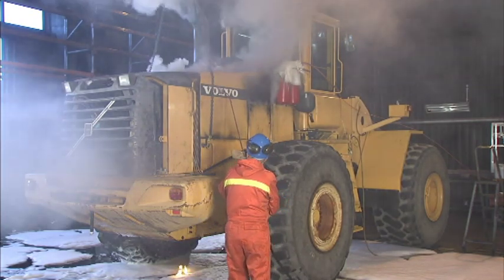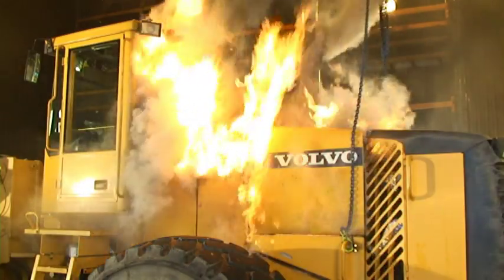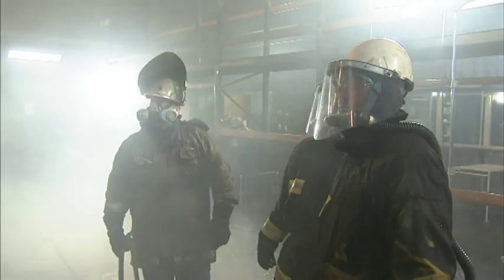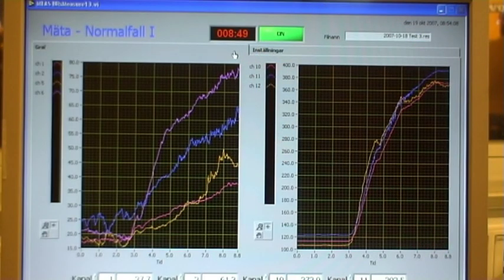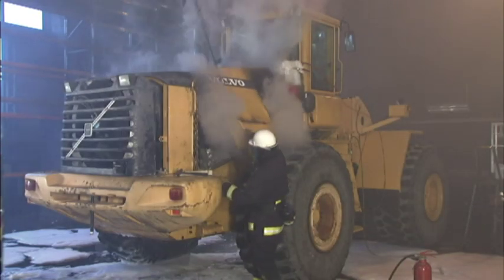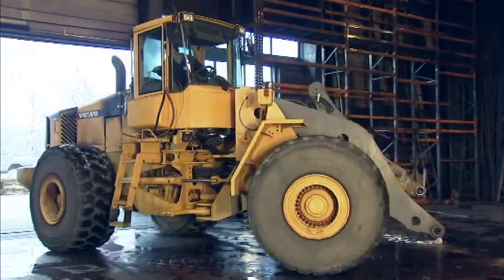After burning for 45 seconds, a further two liters of hydraulic oil is sprayed into the engine compartment with the engine still running. The tests are carefully supervised by experienced firefighters, and staff continuously checks temperatures and other information on the monitor screen in the control room. A full 90 seconds after the fire is ignited, the engine is turned off and the suppression system is activated manually. The temperature in the engine compartment is around 800 degrees Celsius at the moment the liquid is sprayed from the nozzles. The system successfully suppresses the fire, and is now approved in accordance with SBF-127 for construction machines.